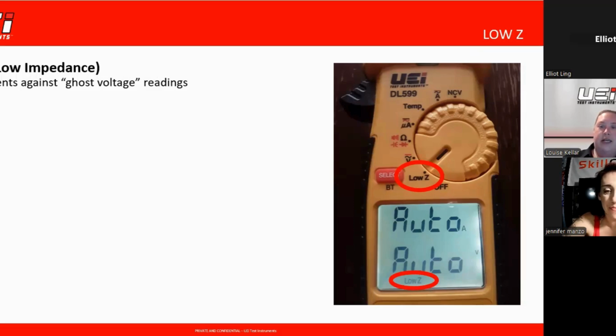When we're working in those very tight spots, what can happen is that you get ghost voltages. What's really happening is the reading is jumping around, picking up interference. So when working in tight, confined spaces, putting your meter in low Z mode when measuring voltage will give you a more accurate reading.